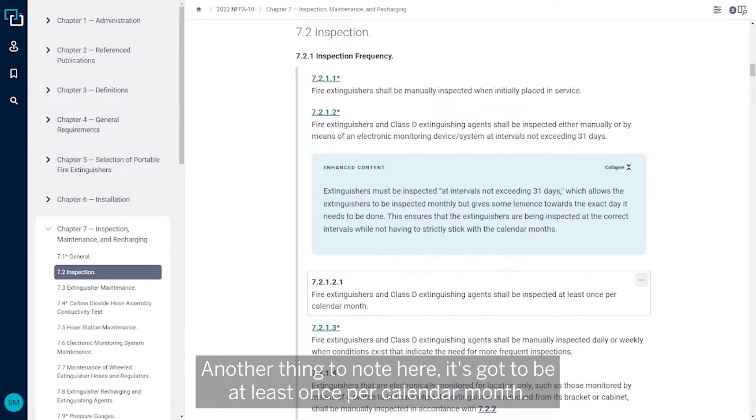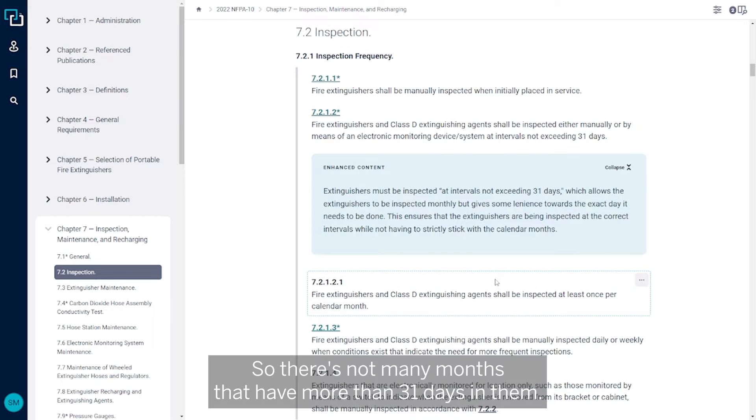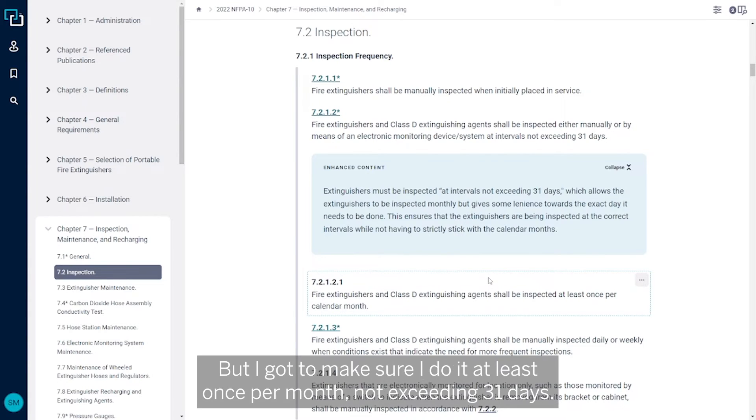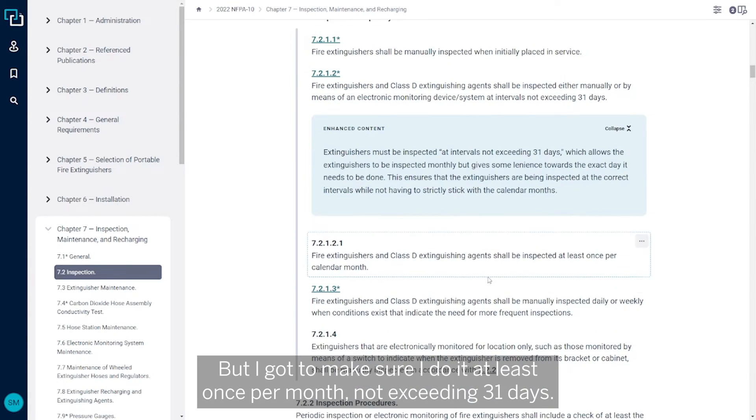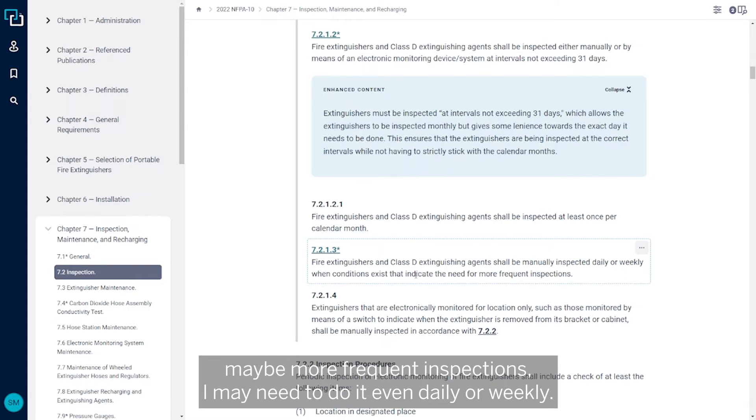Another thing to note: it's got to be at least once per calendar month. So there's not many months that have more than 31 days in them, but I got to make sure I do it at least once per month, not exceeding 31 days. If I'm in an area that conditions require, maybe more frequent inspections, I may need to do it even daily or weekly.